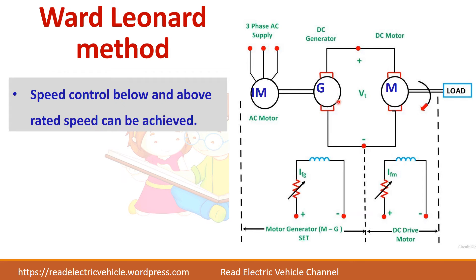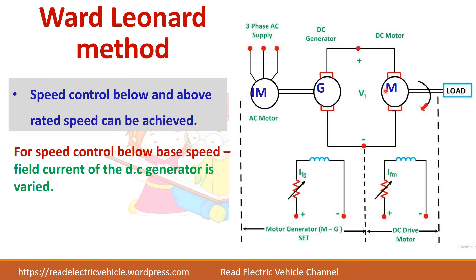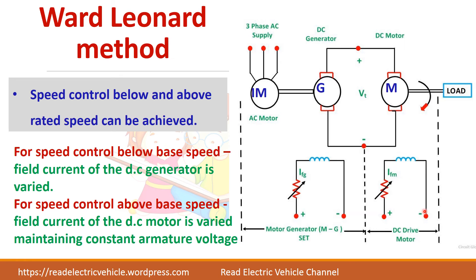Instead of a rheostat, this generator does the function of providing the supply voltage for the motor. If I control the generator output voltage, I can control the voltage applied to the motor. The generator needs mechanical input and gives electrical output. This is the generator field winding and this is the motor field winding. For speed control below base speed, you have to control the field current of the DC generator. For above base speed, the field current of the DC motor can be varied.